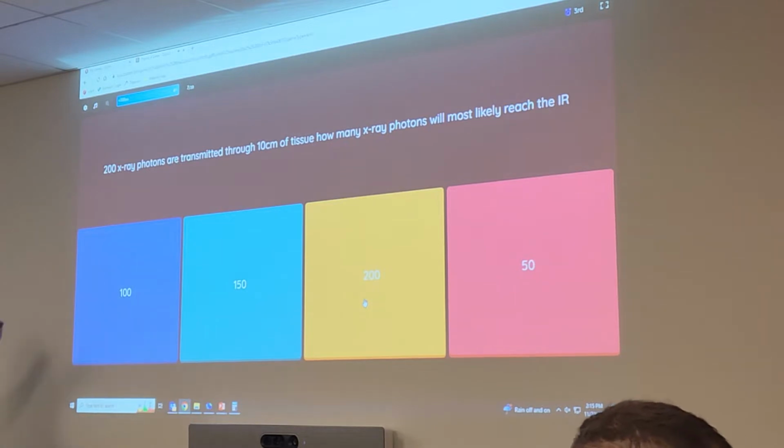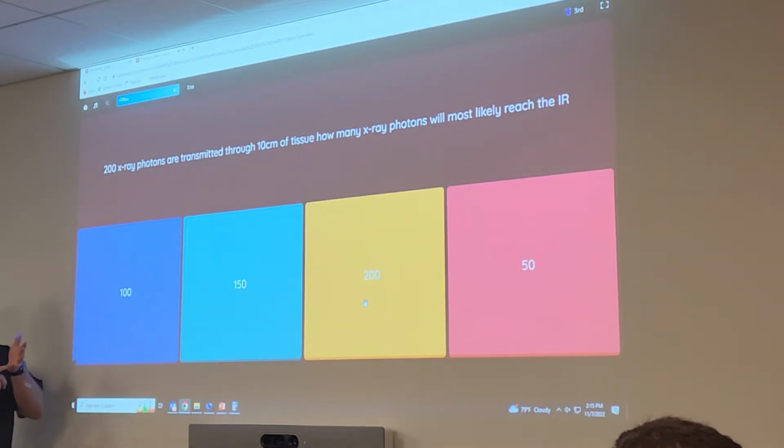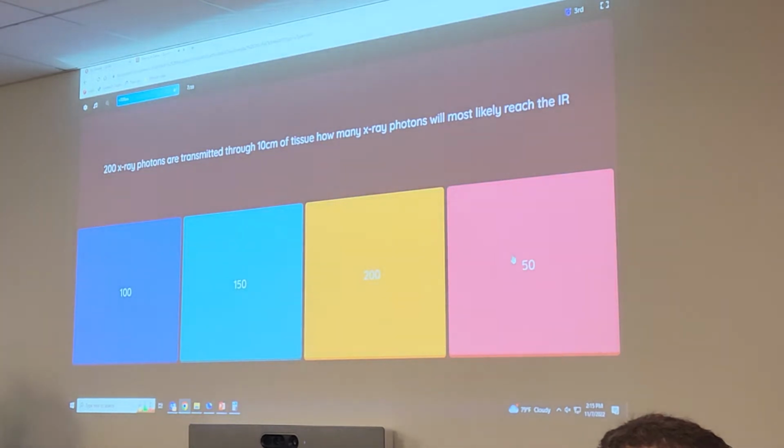But that's what I was saying: if you shoot everybody, for example, at 70 kVp and 4 mAs, everybody gets shot the exact same. How would that differ with patients? You have a baseline for all four body habitus types. So when you type in the exam, it comes up and it's already set, you just go. I don't know if you've noticed, but on the control panel they even have four body types you can pick from, and it'll adjust it. Oh yeah, that makes sense.